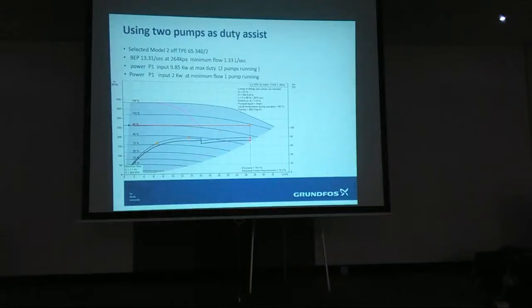Same in heating systems or cooling. What you want to do is get that light shaded band as close as possible to 0 flow. Yeah, but that's what 1/3, 2/3 might do, because if you bring 1/3 in, because it's a smaller pump, you're going to be able to shift that to the left a bit more. On massive systems, yes. If this was something like 80 or 100 litres a second, I would seriously consider using a jockey, particularly when you've got next to no demand at all. And peak demand is way, way out here on the scale of things. In the middle of the night, you don't want anything, you just want to keep the pipe warm, really. Yeah, that's right.